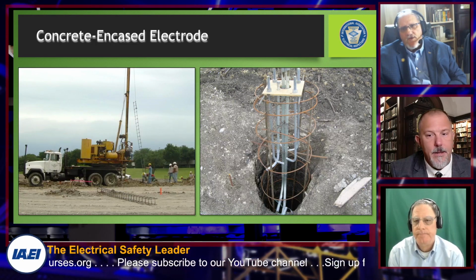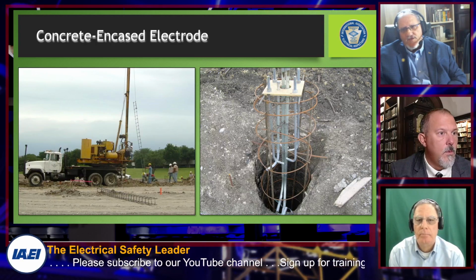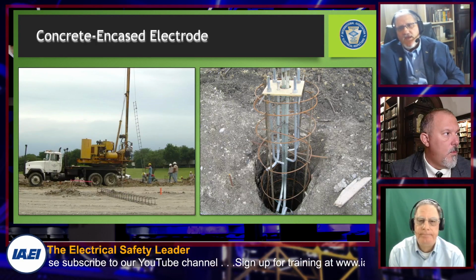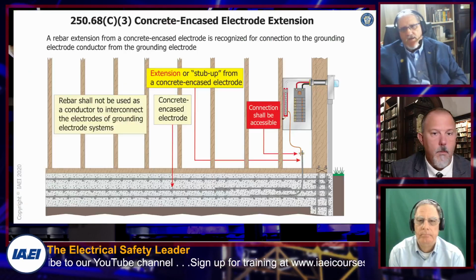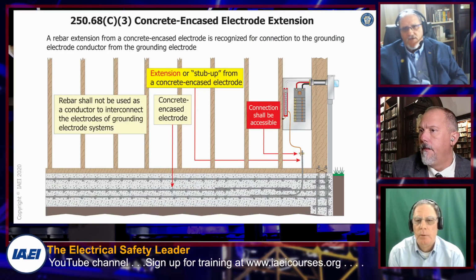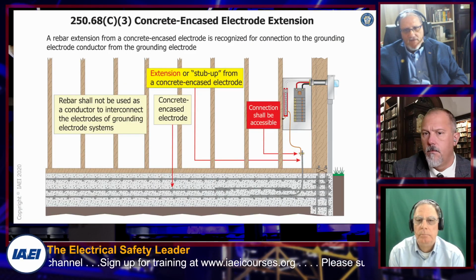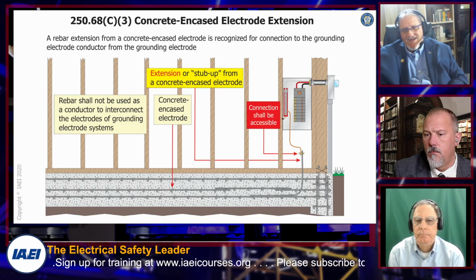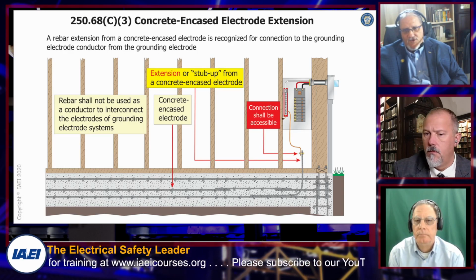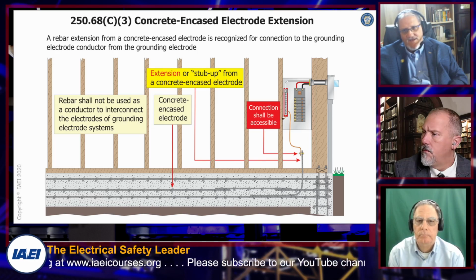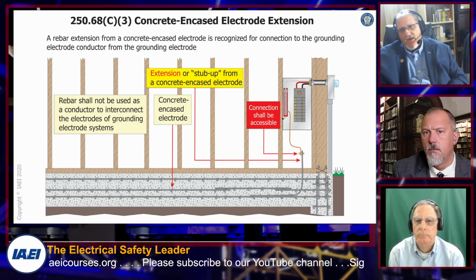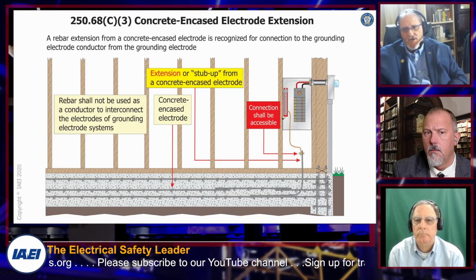That's why the next slide talks about the stub up of a concrete encased electrode. People get hung up on that one a lot too. I always say, and Chuck, verify this, that something has to qualify as a concrete encased electrode by meeting the 4 conditions.